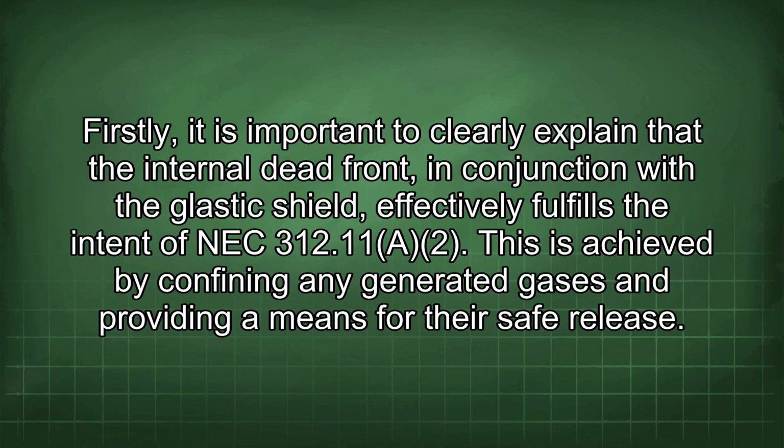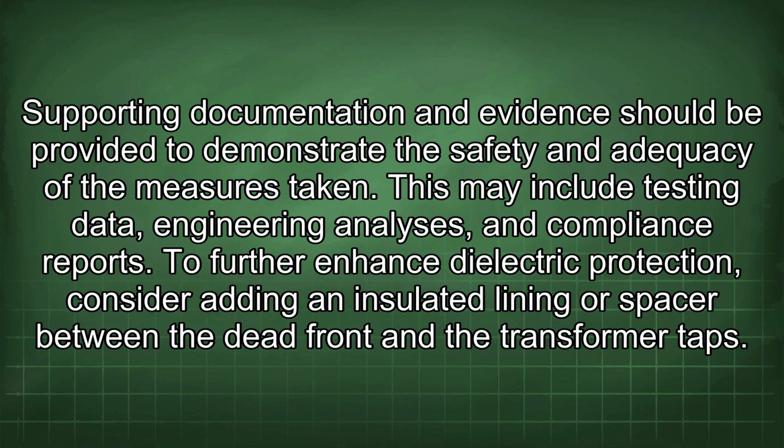Firstly, it is important to clearly explain that the internal dead front, in conjunction with the glastic shield, effectively fulfills the intent of NEC 312.11(A)(2). This is achieved by confining any generated gases and providing a means for their safe release. Supporting documentation and evidence should be provided to demonstrate the safety and adequacy of the measures taken. This may include testing data, engineering analyses, and compliance reports.